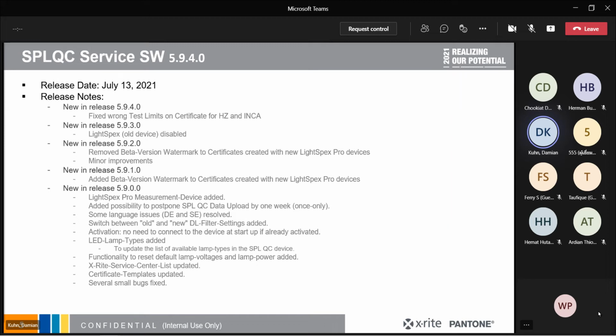But even if these partners or users did replace the bulbs, they were still stuck in that workflow where, whenever they wanted to calibrate the SPLQC device, it automatically shut off that light source with the overcurrent message. The new service software allows you to set the lamp voltage for a selected light source back to a default value, and then you should be able to go back to that light source and recalibrate it without that overcurrent message occurring on the screen. We're going to see how that can be done when we look at the software in about 5 minutes. Other changes we made are a couple of bug fixes and a couple of changes to the certificate templates.